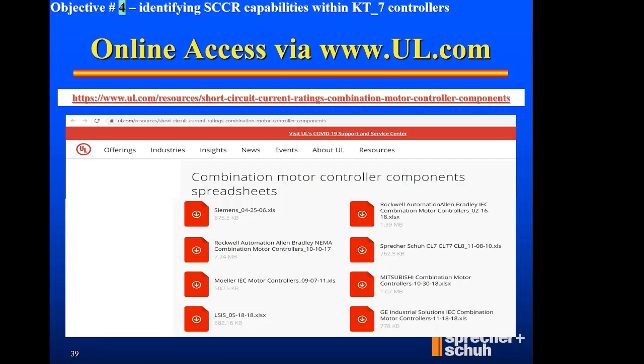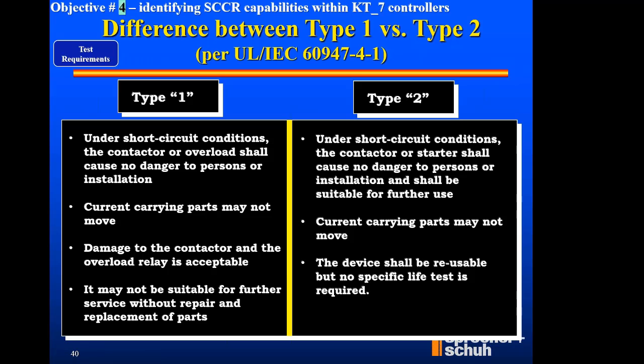Now, I just showed you how Sprecher and Schuh has a coordination of controller plus a contactor. I digress just a little bit to say that we as manufacturers are required to submit a spreadsheet to UL so that UL could keep these spreadsheets posted on their public website. So you can go look at our rating spreadsheet and table that we submitted with UL, and just go to ul.com and search short circuit combination motor controllers, and you'll find all the different manufacturers listed with the different spreadsheets. And absolutely, you'll find Sprecher and Schuh CL7, CLT7, CL8 kinds of spreadsheet approvals. So I digress just to let you know you can go to a public UL site to see our spreadsheet as well as all the competitor spreadsheets.